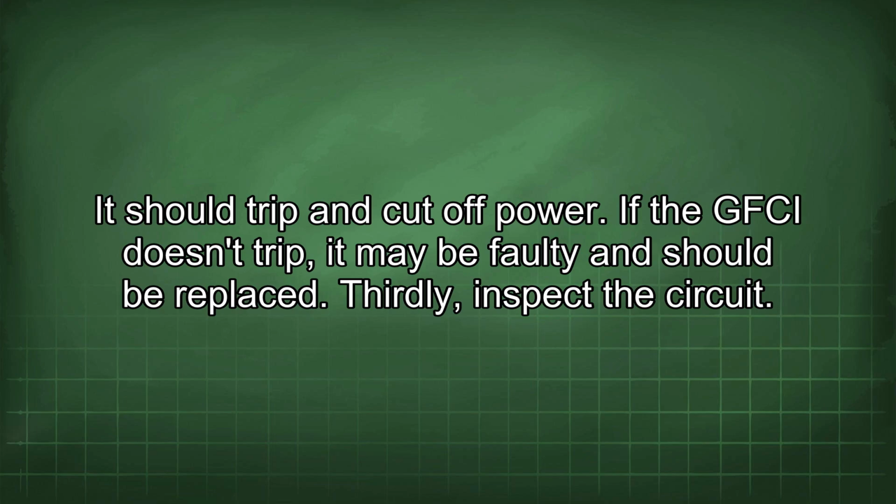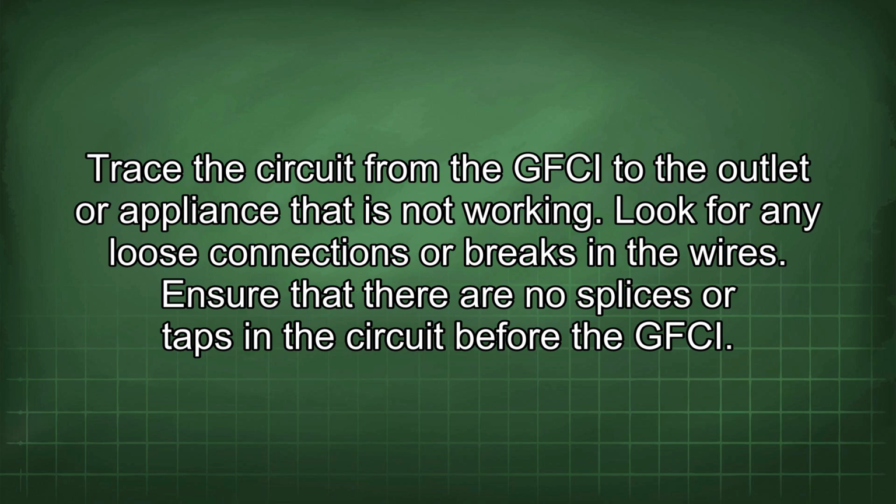Thirdly, inspect the circuit. Trace the circuit from the GFCI to the outlet or appliance that is not working. Look for any loose connections or breaks in the wires. Ensure that there are no splices or taps in the circuit before the GFCI.